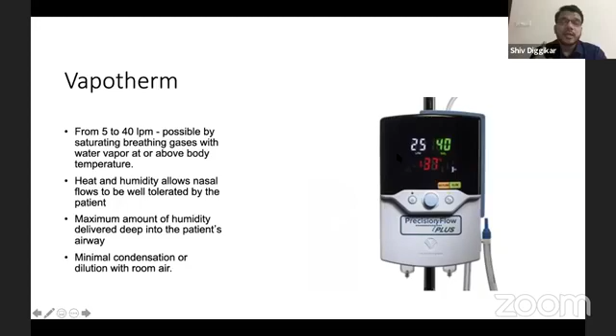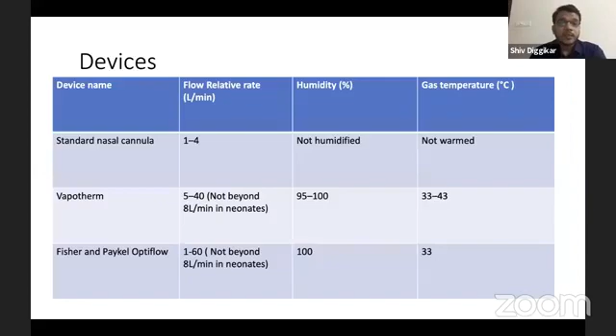Vapotherm, again, you can provide, it looks like this. This is the equipment, again a standard equipment to provide the HFNC. You can adjust the flow rate anywhere from 5 to 40 liters, humidified to 34 to 37 degrees Celsius, and heated to about 37 degrees Celsius. Okay, so you can provide 5 to 40 liters. Again, beyond 8 liters, it's not recommended.